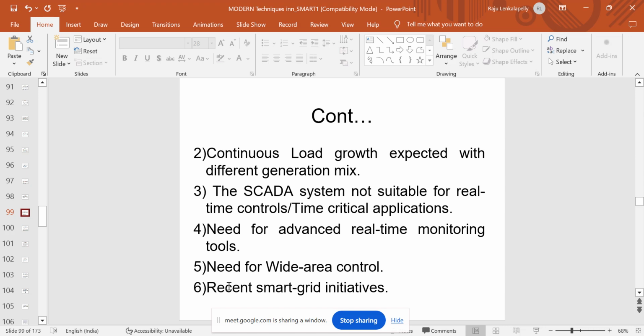What do we mean by real-time control? As mentioned, RTUs collect data, convert it from analog to digital, and send it through a fiber optic communication channel to the load dispatch center. There, several applications are performed, such as load flow or automatic generation control. For example, the output from load flow is voltage magnitude and phase angle. If the voltage magnitude at a particular bus is not within the limits of plus or minus 5%, there is a problem.